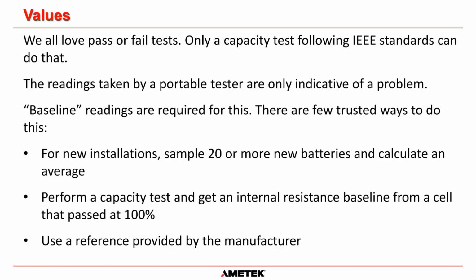So that's how the testers test the battery. But what do we do with the values? What are we looking for? And, you know, we all love pass or fail tests. They're the easiest ones to analyze. But only a true capacity test following IEEE standards can do that. That is the only way you can pass or fail a battery, okay? The readings taken by a portable tester, they're only indicative of a problem. They're not telling you that there absolutely is a problem. It's indicating that there may be a problem, okay?